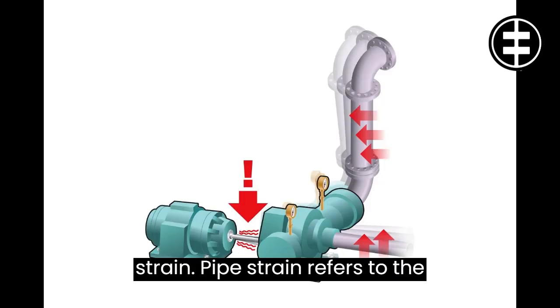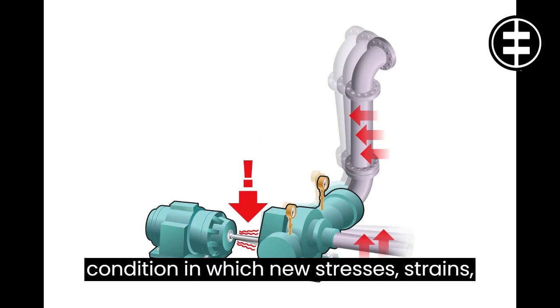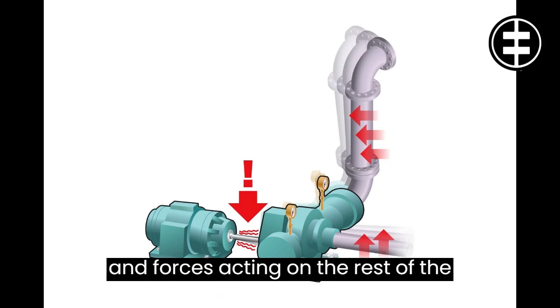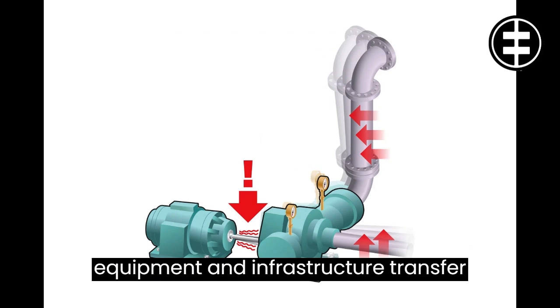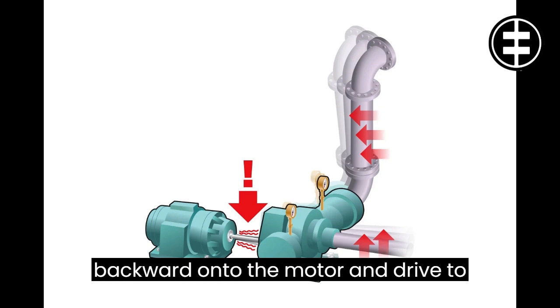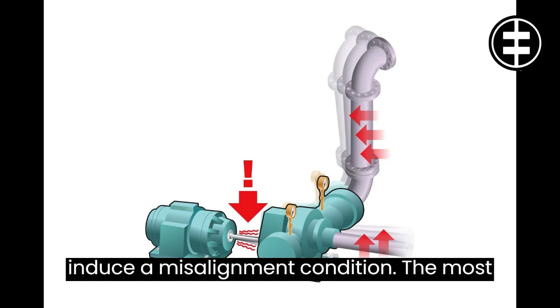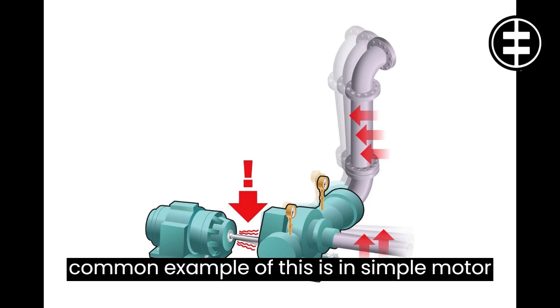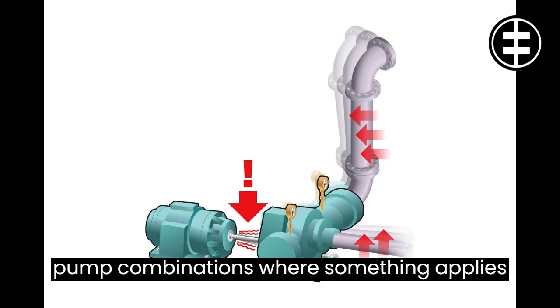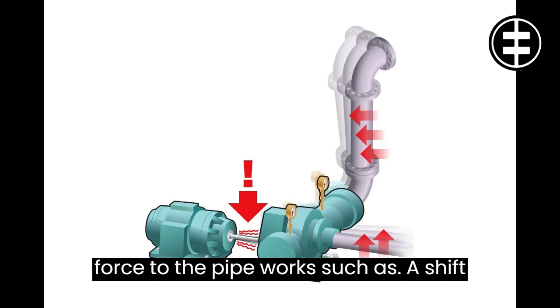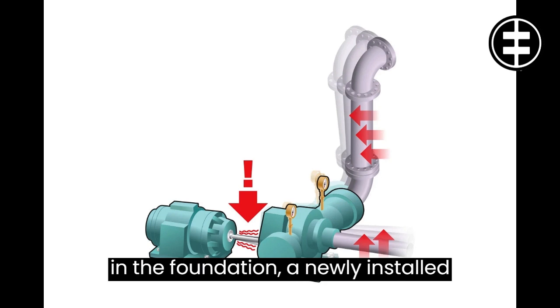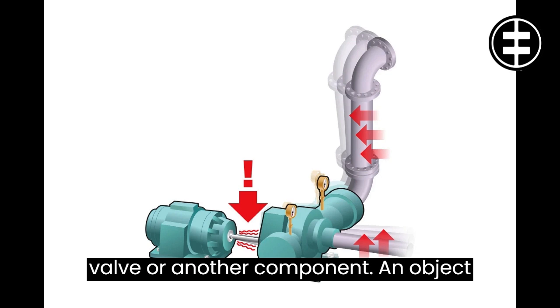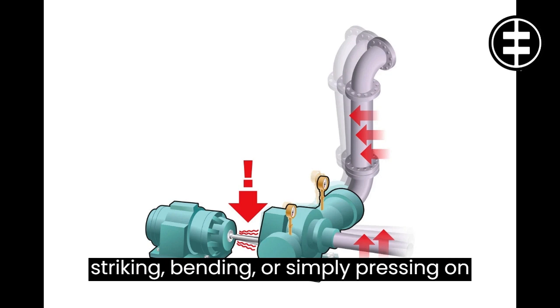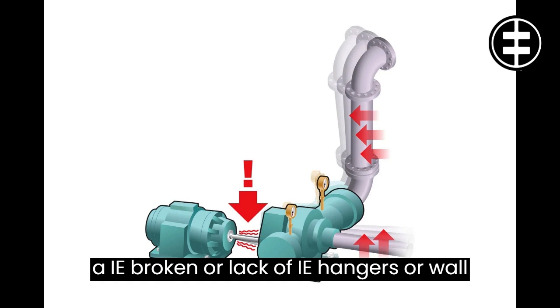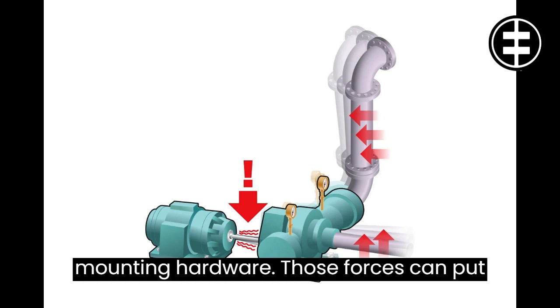12. Pipe strain. Pipe strain refers to the condition in which new stresses, strains, and forces acting on the rest of the equipment and infrastructure transfer backward onto the motor and drive to induce a misalignment condition. The most common example of this is in simple motor pump combinations where something applies force to the pipework, such as a shift in the foundation, a newly installed valve or another component, an object striking, bending, or simply pressing on a pipe, broken or lack of pipe hangers or wall-mounting hardware.